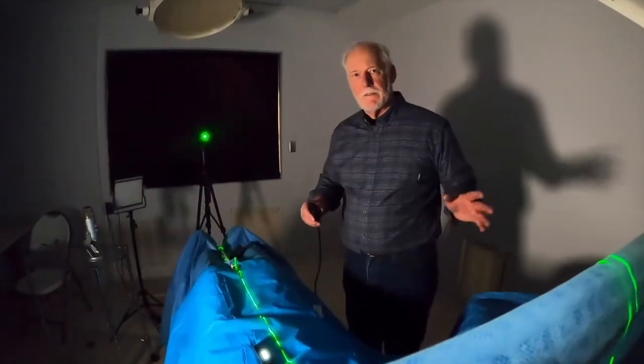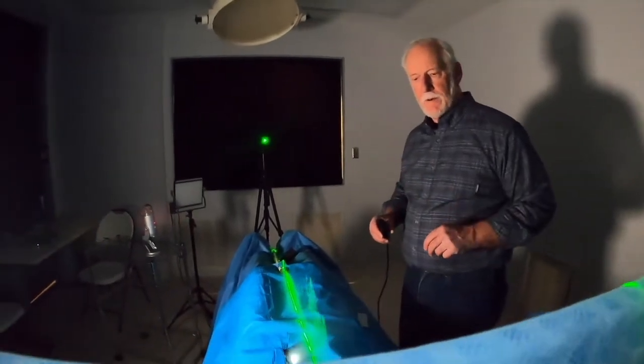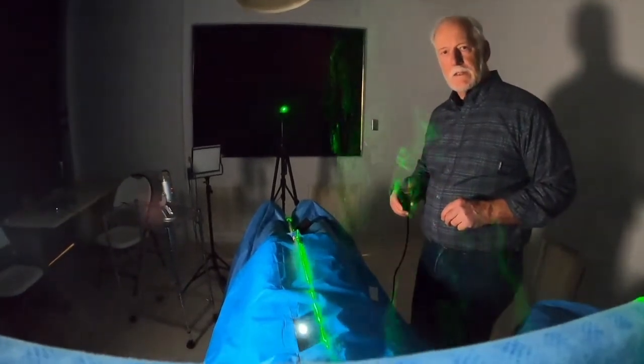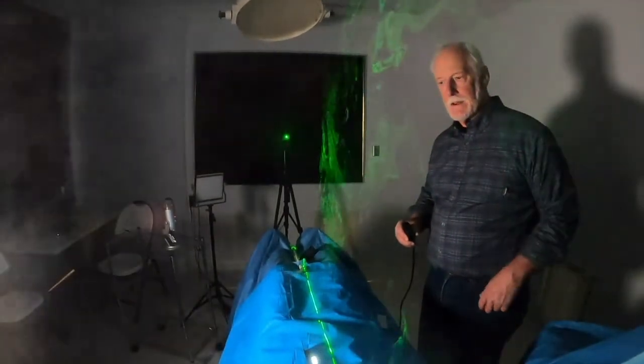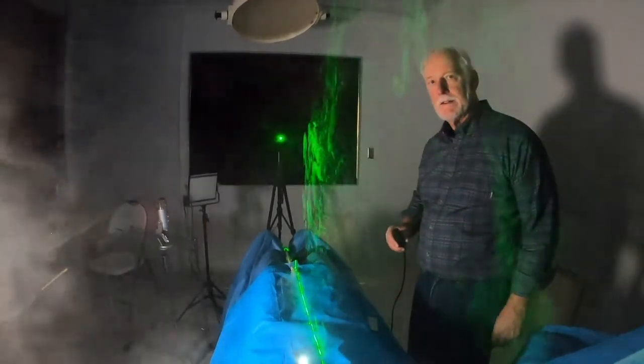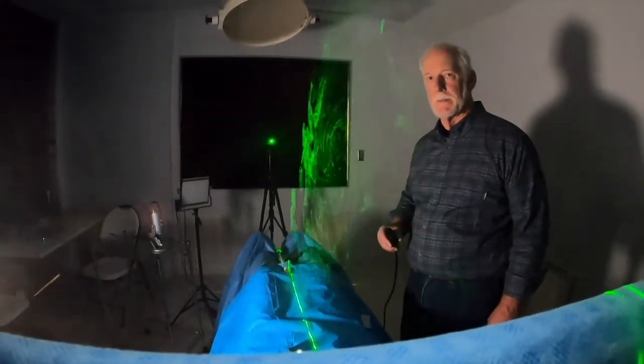We still have the forced air system going, and we're just taking this from a different angle. You saw the green laser before, and now we're going to see what the smoke looks like looking down that green laser. You can see it forming into a vortex, you can see it circulating around, and you can see it staying airborne for a good long while. Once again, none of that smoke should be there — it is totally due to the forced air warming.